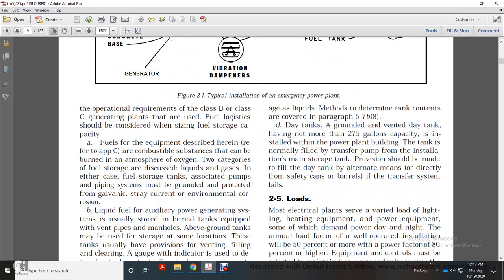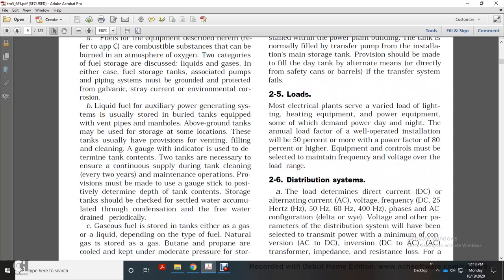The operational requirements of Class B and Class C generator plants and fuel logistics should be considered when sizing fuel storage capacity. Fuel, as referred to in Appendix C, is a combustible substance that can be burned in atmospheric oxygen. Fuel storage categories include liquid and gas. In either case, the fuel storage tank, associated pumps, and piping system must be grounded and protected against galvanic stray current and environmental corrosion. Liquid fuel for auxiliary power generator systems is usually stored in buried tanks. Tanks must ensure continuous supply during tank cleaning, with maintenance required approximately every two years.